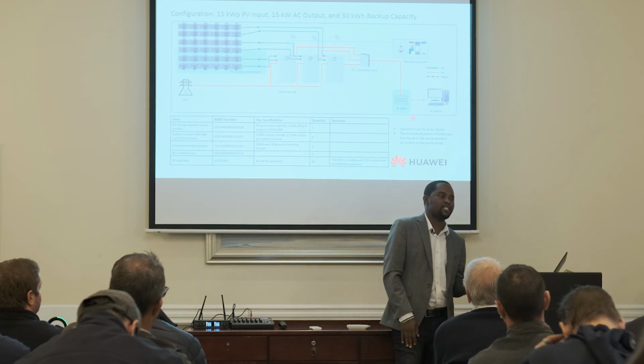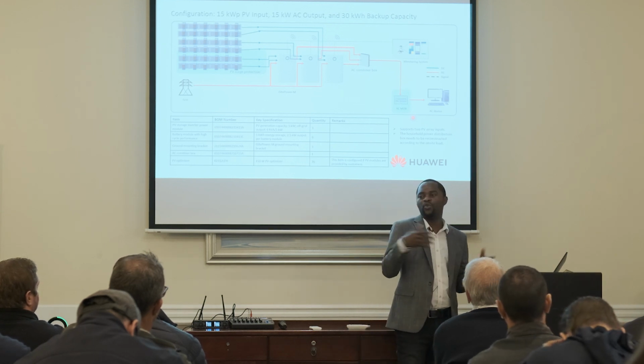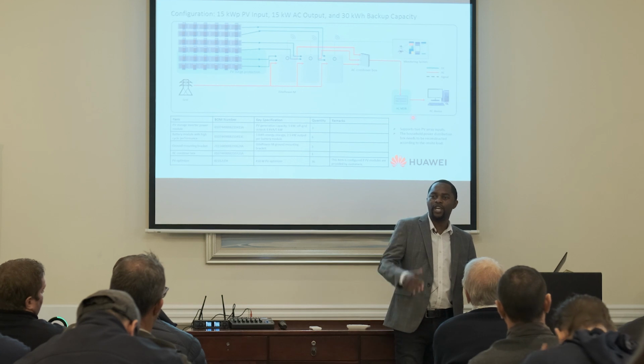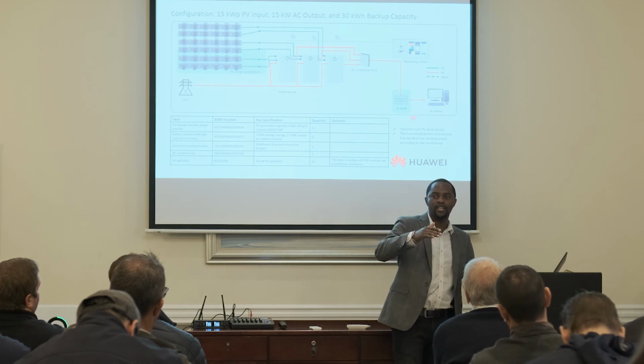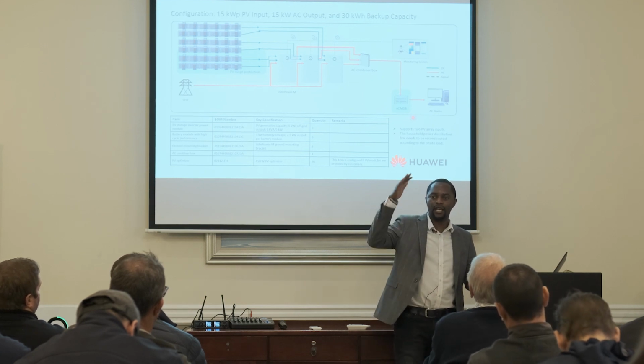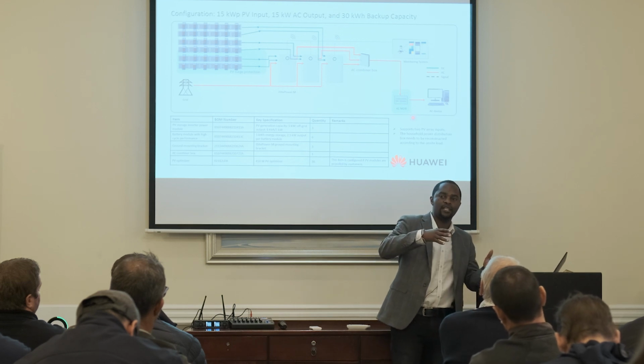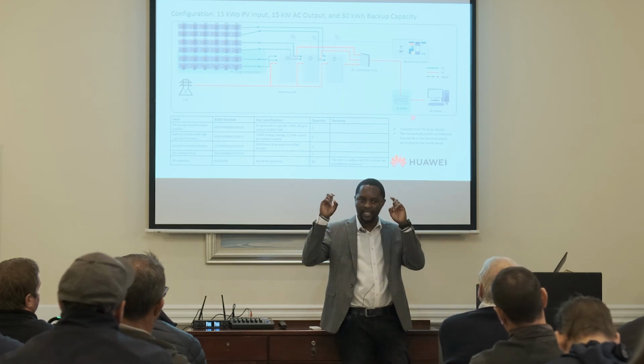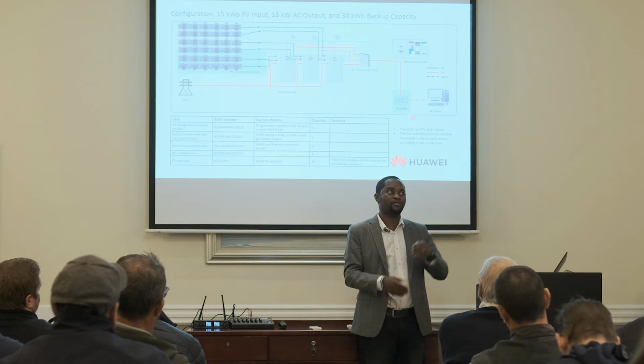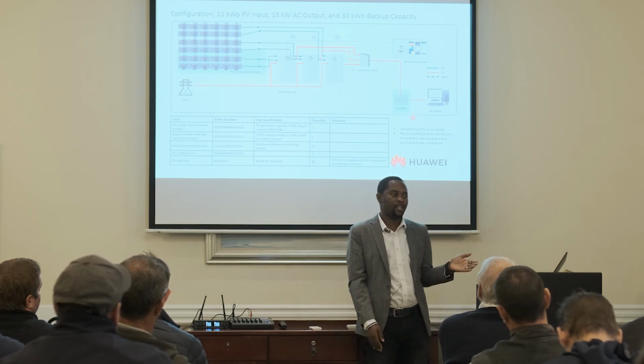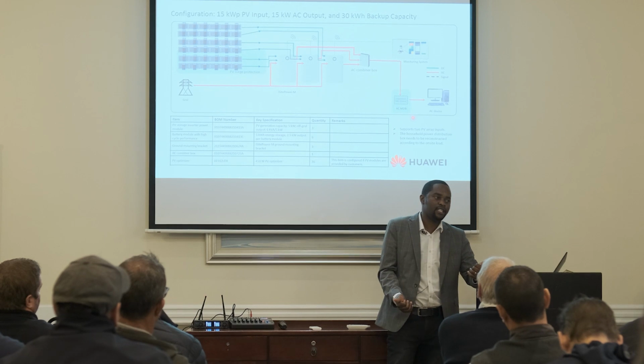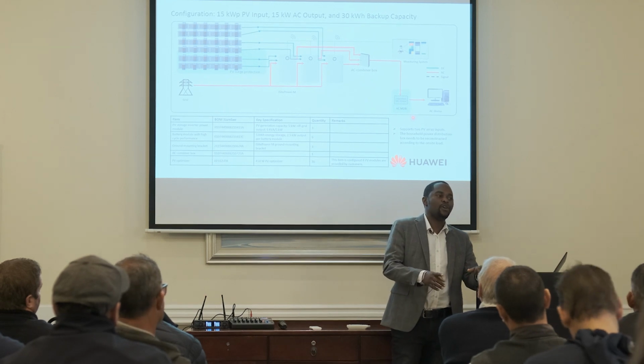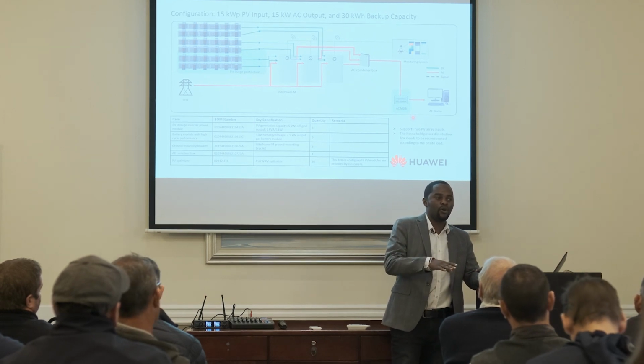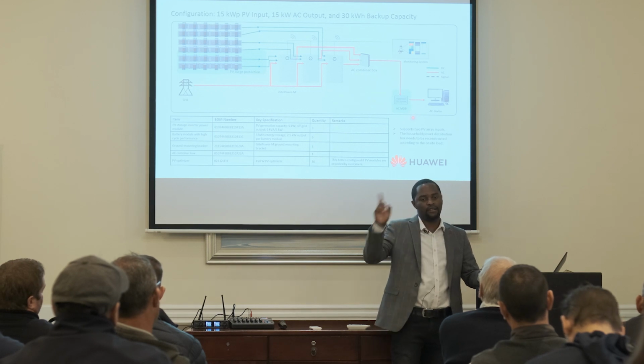There's no need of keeping your batteries at 70% for 2 weeks when there's no load shedding. So you can lower that to 30% so that your batteries are cycling and discharging. You are charging from the sun, and during the night you're using that solar energy instead of taking from the grid. But if you put it up higher, it's safe for the end user, because they know that if they've got load shedding anytime, they are covered. But then during the night, when PV is low or zero, you are forced to take from the grid.